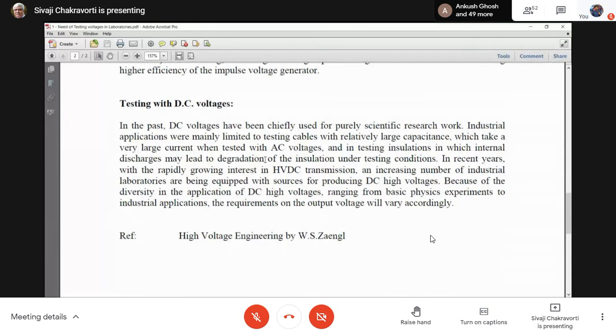Yes, the common way is that you have to reduce the voltage first by some proportional mechanism. There are two very common mechanisms. One is called a potential transformer. The second is called a potential divider. Then we measure the low voltage, and if we know the ratio of transformation, I can calculate the high voltage. So we can see that there are issues involved in measuring very high voltages, which are not of the order of say 200 volts or 300 volts, but of the order of several tens and hundreds of kilovolts.